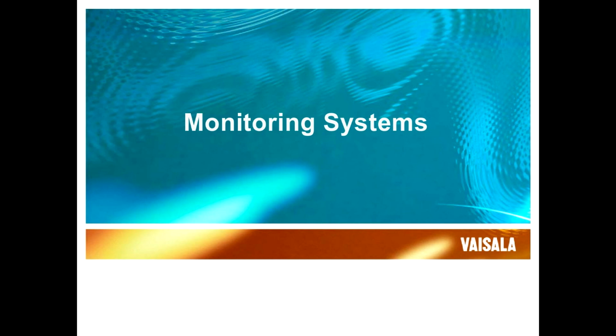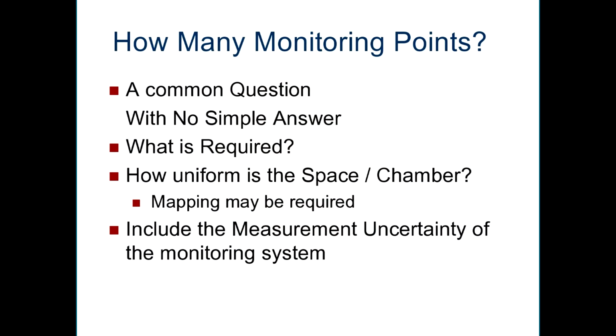Now let's look at the needs of an RH monitoring system. A question I frequently get asked is, how many monitoring points do I need? Unfortunately, there's no simple answer. It really depends upon what the application requires. How tight a humidity uniformity do you need in a chamber or in a room? And how uniform is the space or chamber to begin with? You may need to map the chamber or room if you need a very tight uniformity. That will give you a good idea of how many monitoring points you may need.